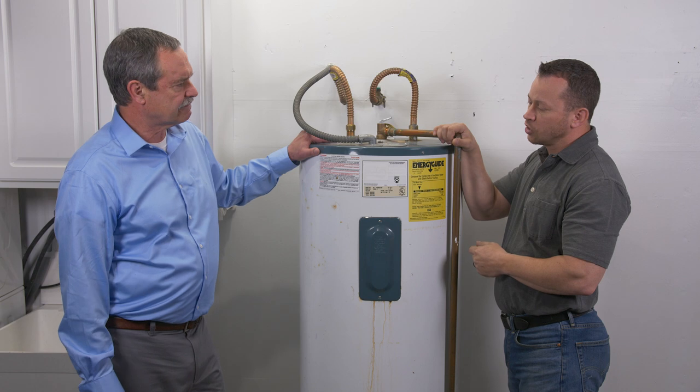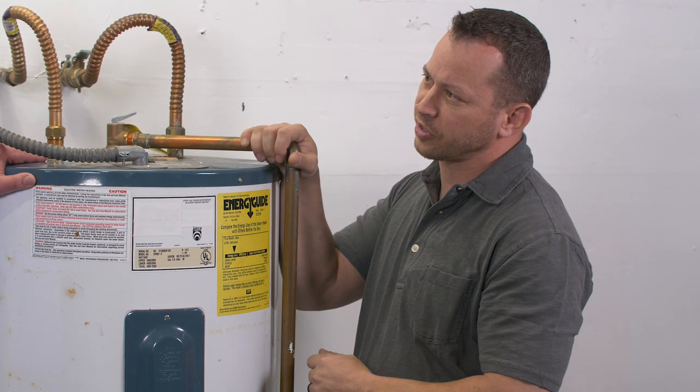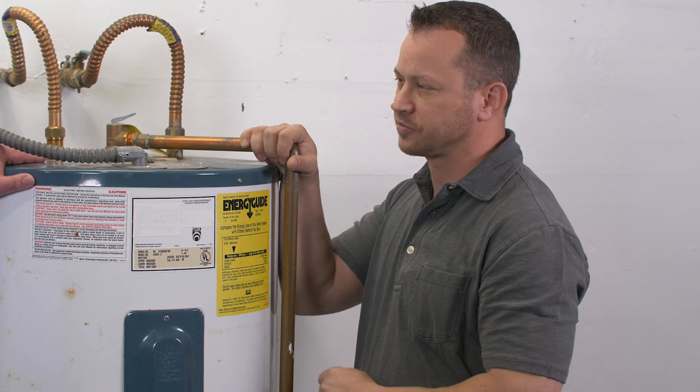I see some tanks going with expansion tanks. When does code require an expansion tank? Whenever the system is closed, and we have an open system here, but if you had a backflow preventer on your house or something like that, of course, we have to have some expansion.